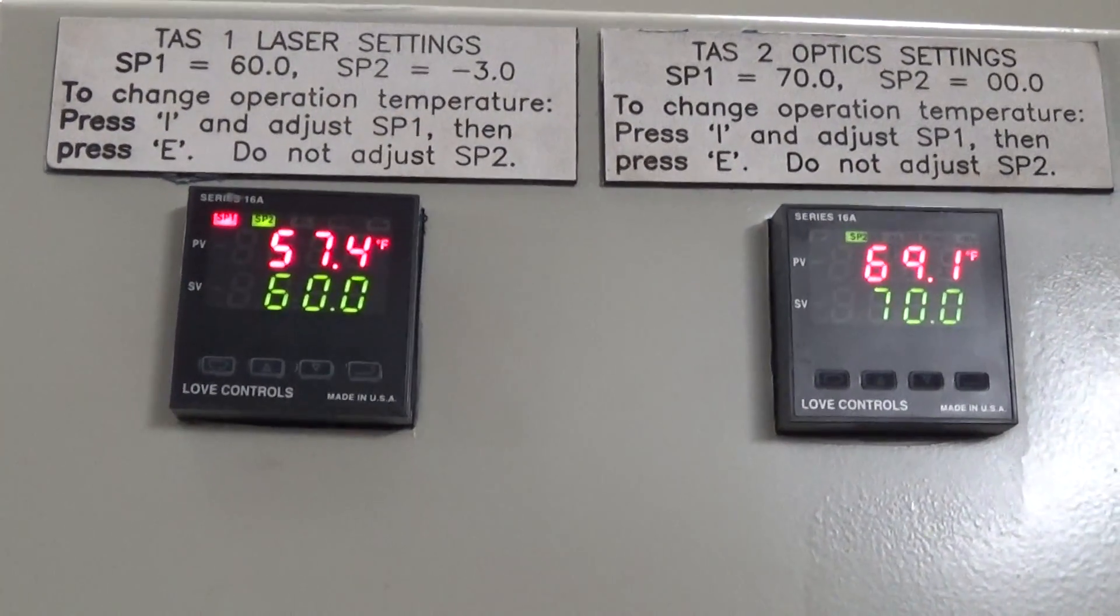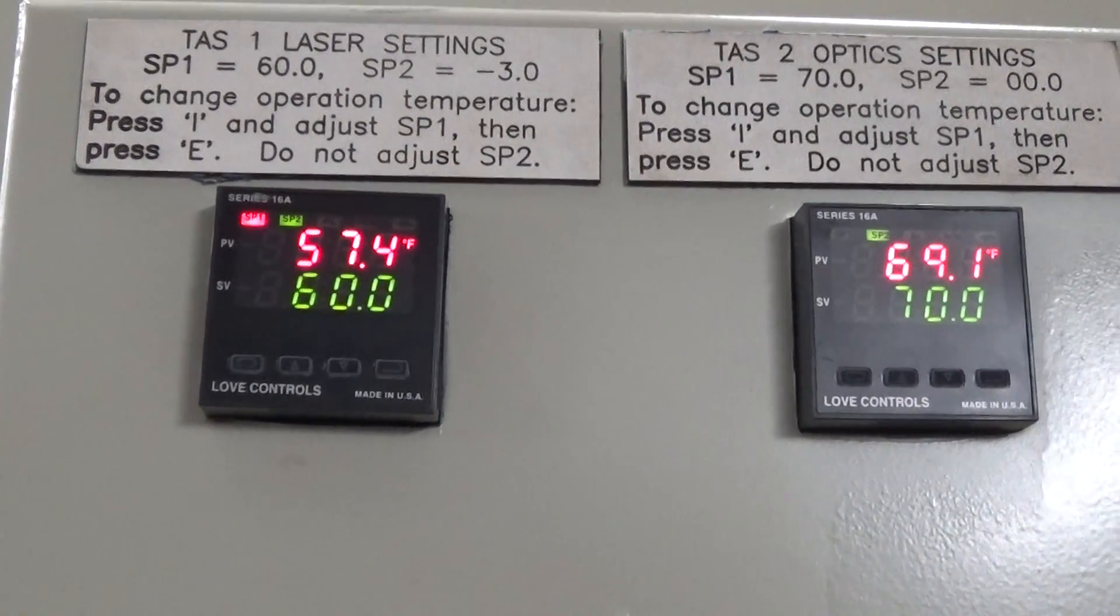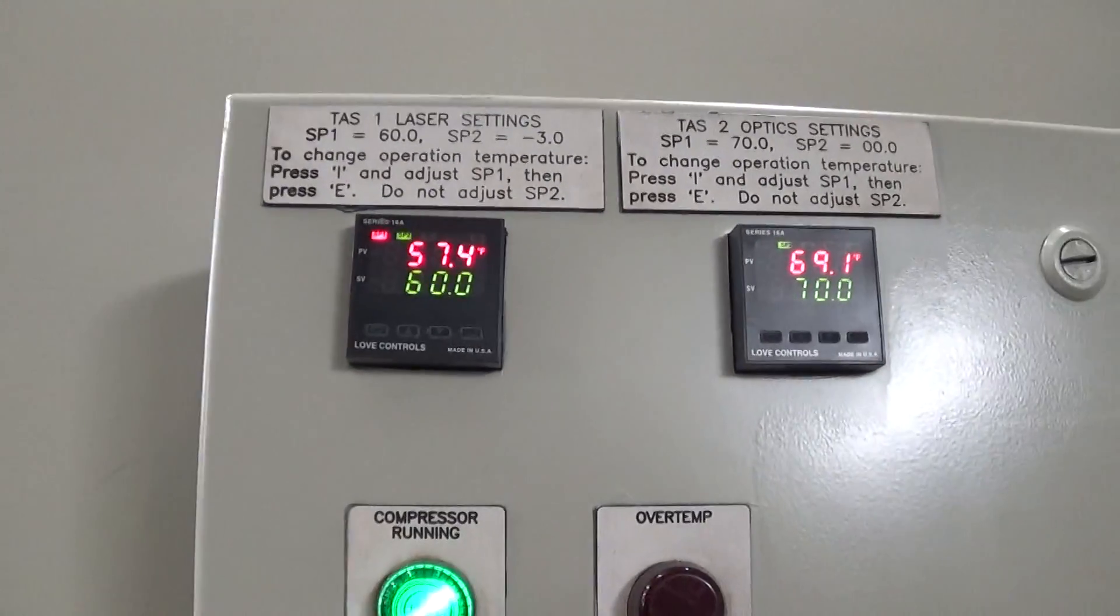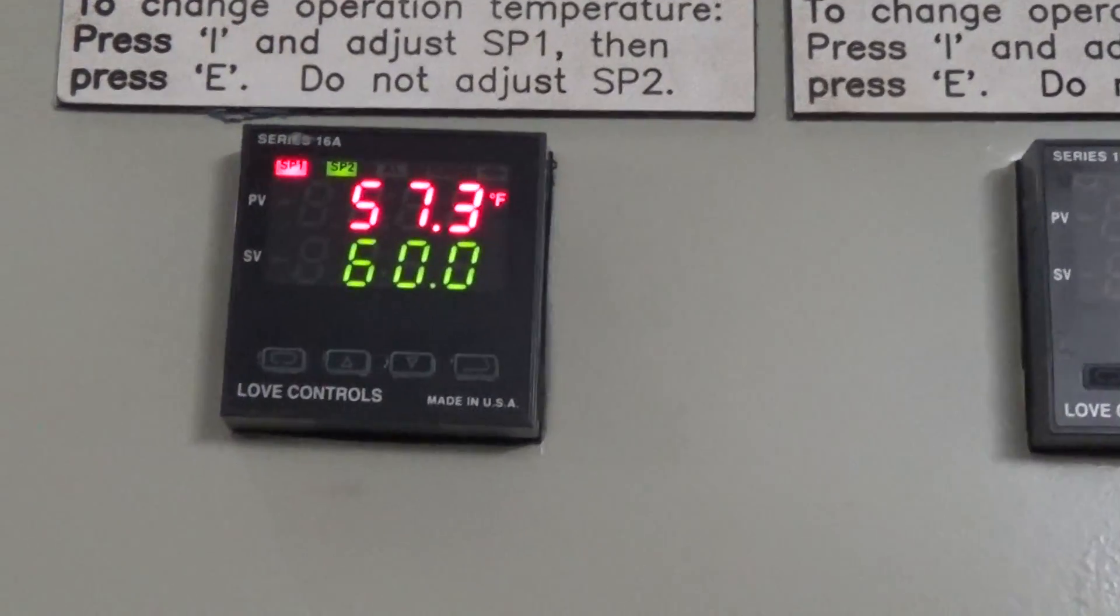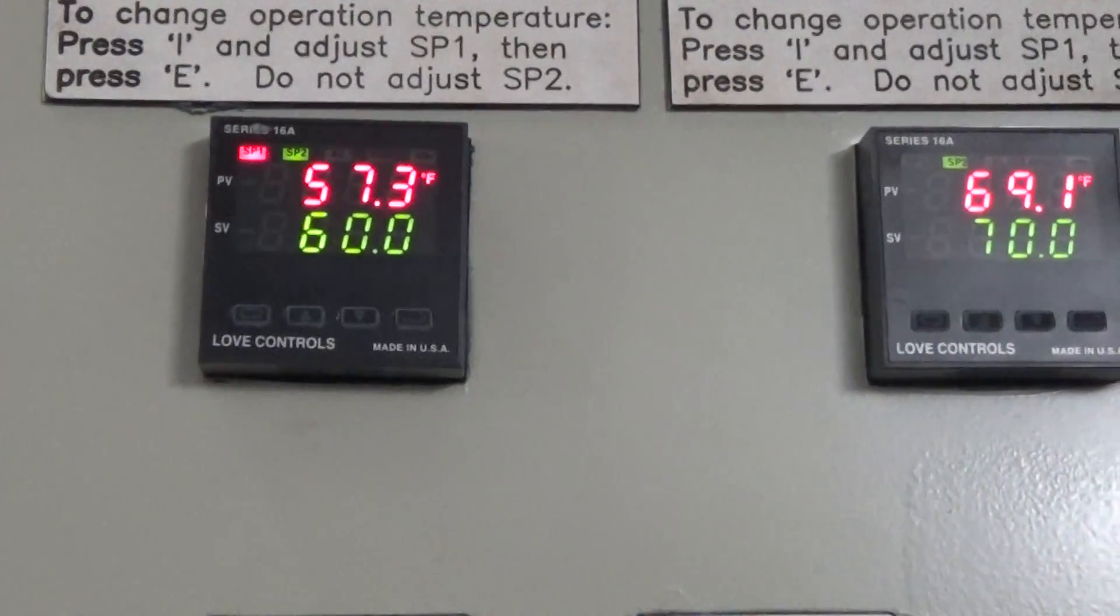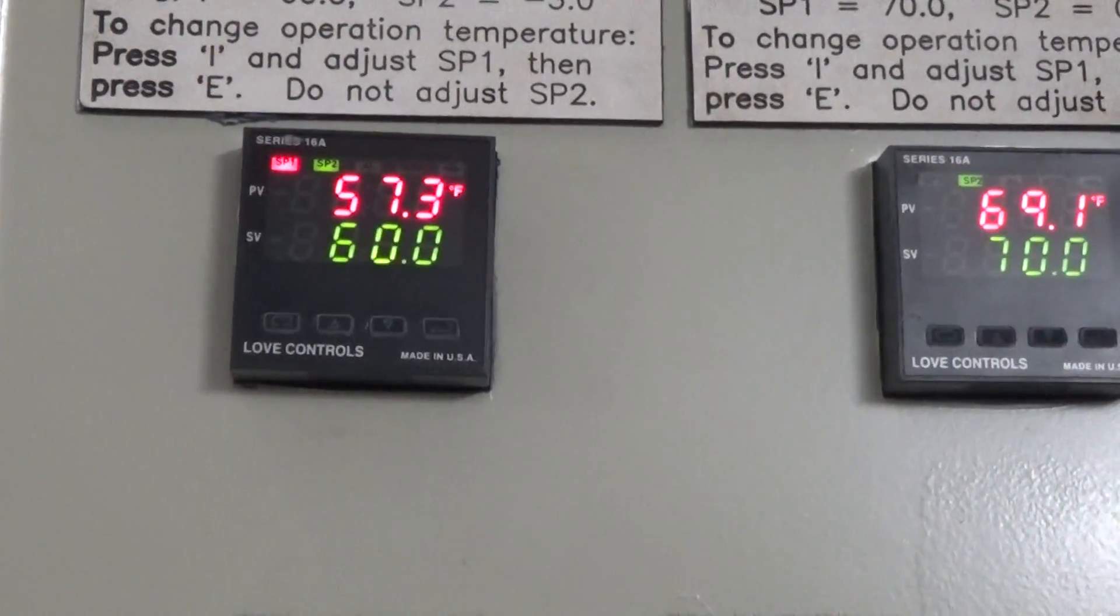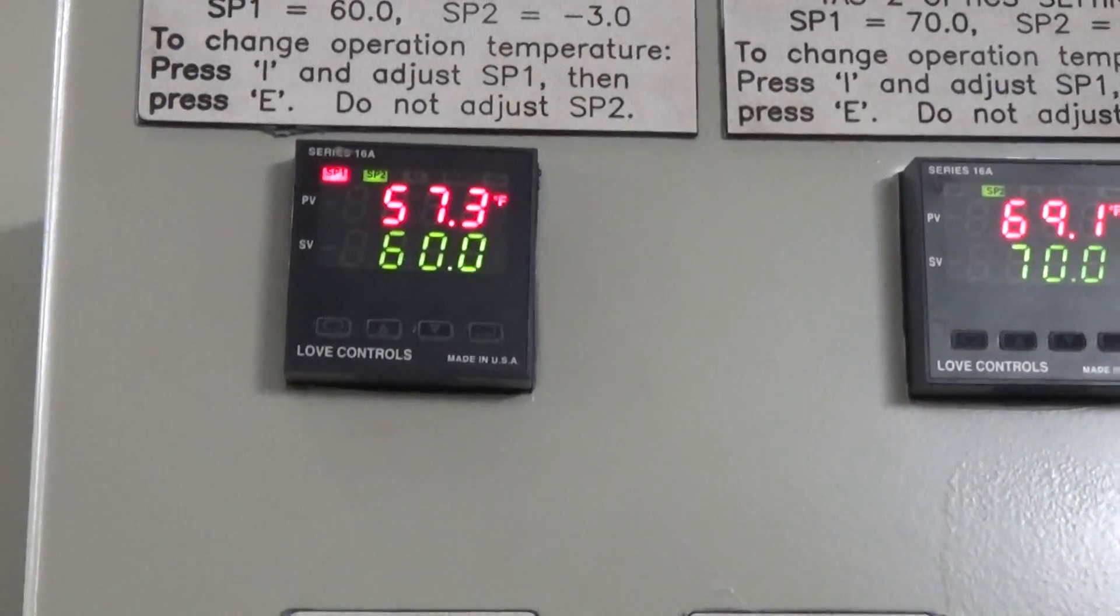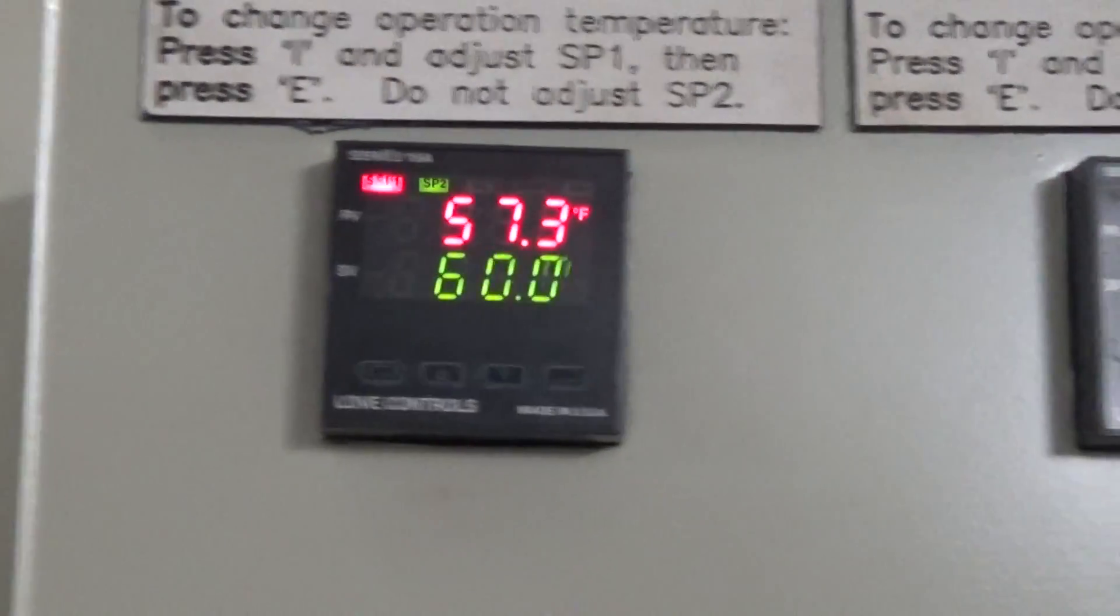So 57.4 and once we reach 57 that's when it should turn off. It is in hot gas mode right now which is an algorithm within the controller to control the hot gas to give kind of a false load to leave the compressor running as much as possible and steadily.